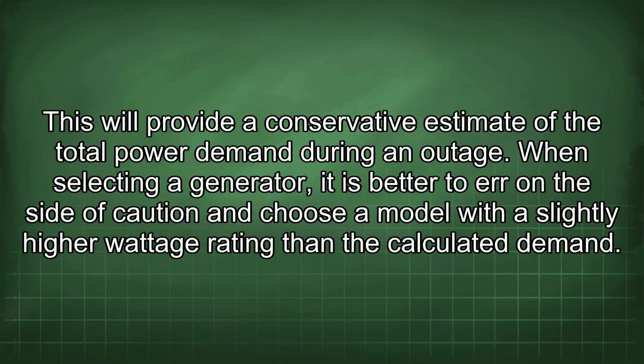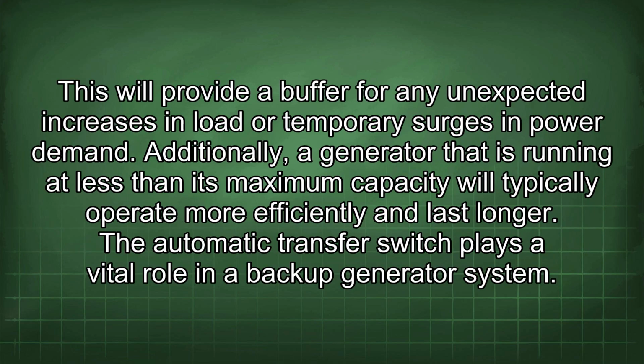This will provide a conservative estimate of the total power demand during an outage. When selecting a generator, it is better to err on the side of caution and choose a model with a slightly higher wattage rating than the calculated demand. This will provide a buffer for any unexpected increases in load or temporary surges in power demand. Additionally, a generator that is running at less than its maximum capacity will typically operate more efficiently and last longer.